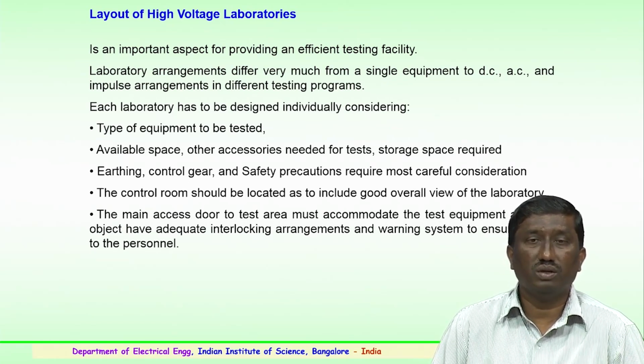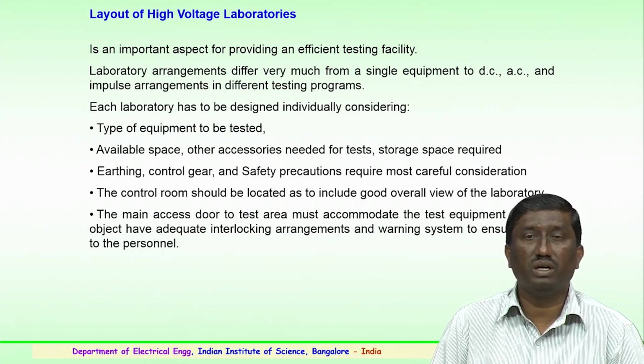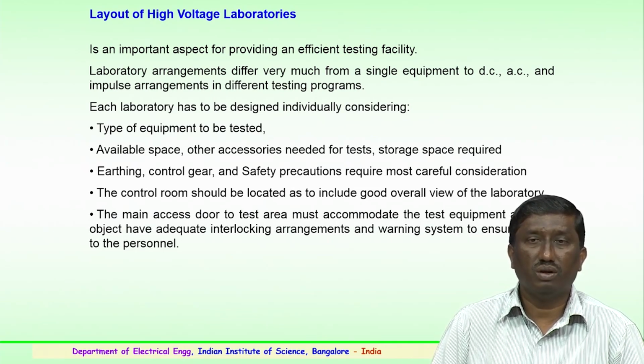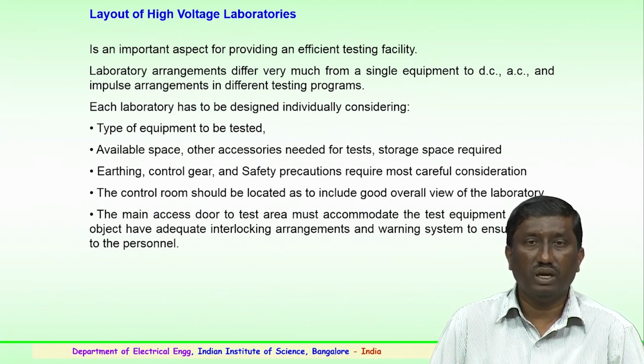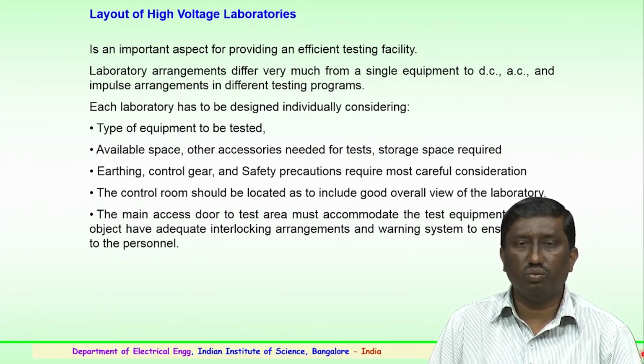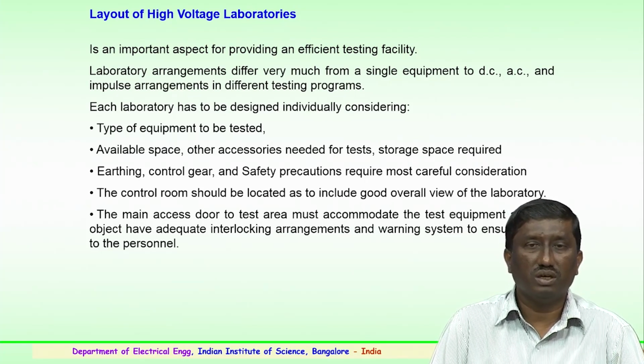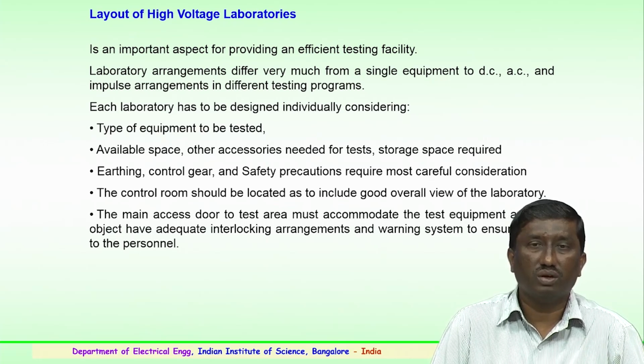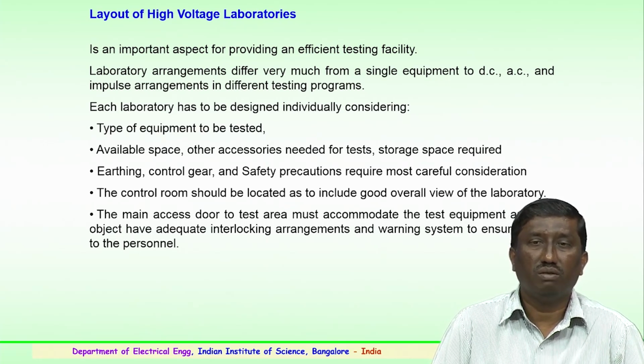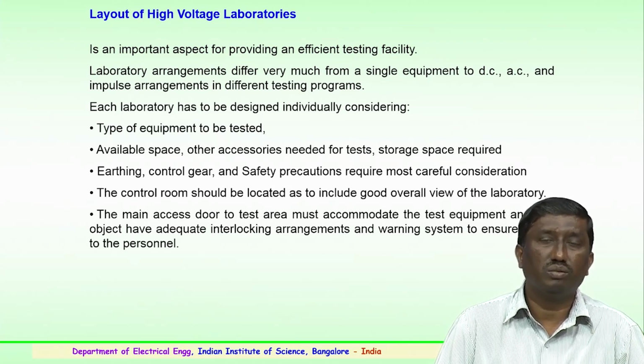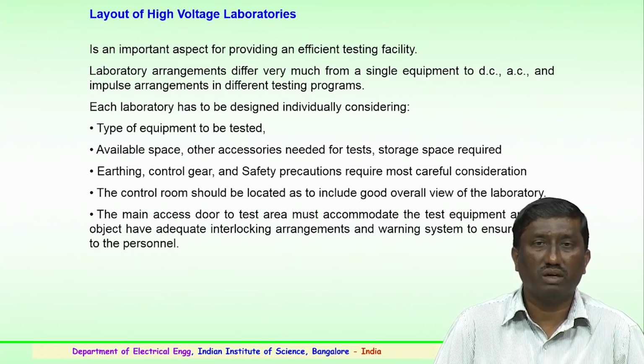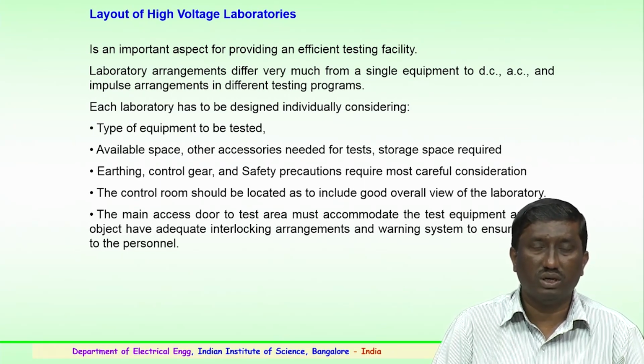The control room facilities should be located so that they include a good overall view of the entire laboratory, preferably. The main access door entering the laboratory to the test area must accommodate the entire test equipment and the test object, have adequate interlocking arrangements, and there should be a warning system available, particularly to ensure safety to the personnel who are involved in the testing activities at the high voltage laboratories.